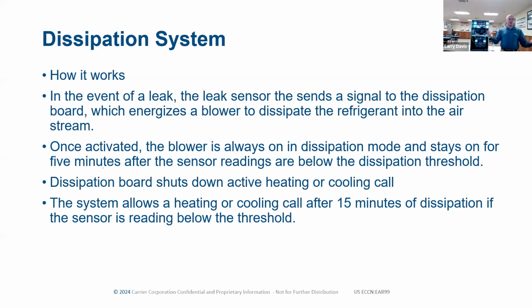Once that sensor has cleared, it goes for a 15-minute total dissipation. It's going to be in dissipation for at least 15 minutes. And then once it sees that it's staying below that threshold, it will actually allow the system to go back to heating or cooling. Now, obviously, if we've had a refrigerant leak, our cooling's not going to work. So you're going to get called out on a no cooling call, but it does allow the furnace to kick on because we've mitigated the amount of refrigerant that's in the air. We're well below any concern for flammability there.